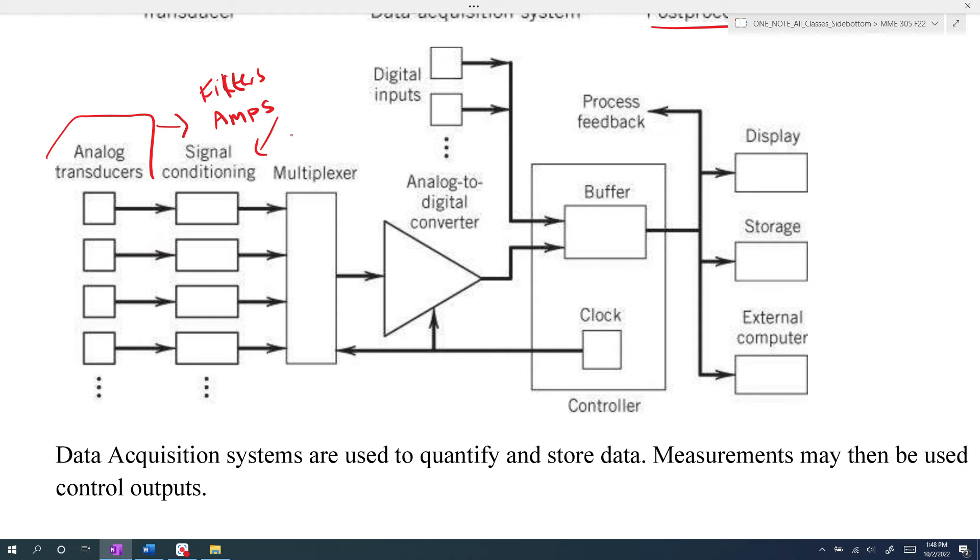So after the signal has been conditioned, it goes into a multiplexer, and then that multiplexer basically directs the different channels into an analog-to-digital converter. And then the analog-to-digital converter goes to our device, and typically the device will also have some type of control that might affect the feedback and affect the signal going forward.